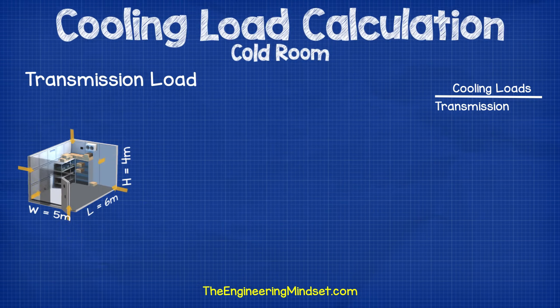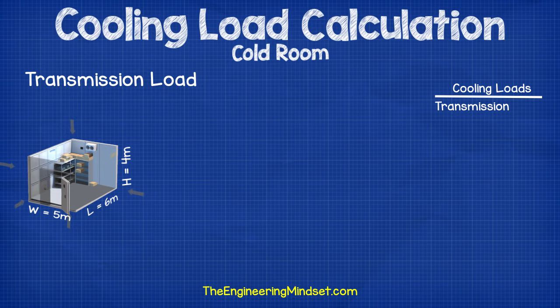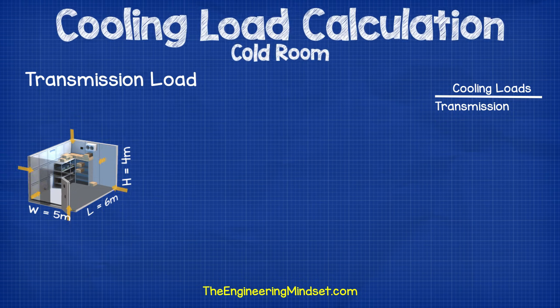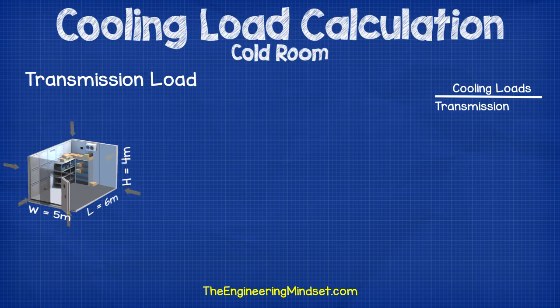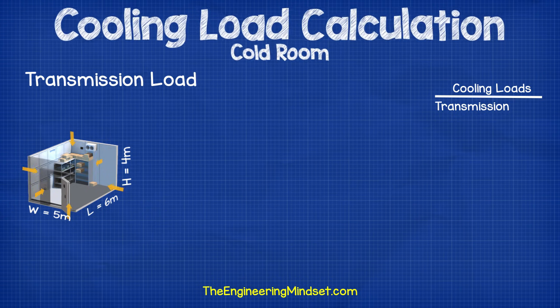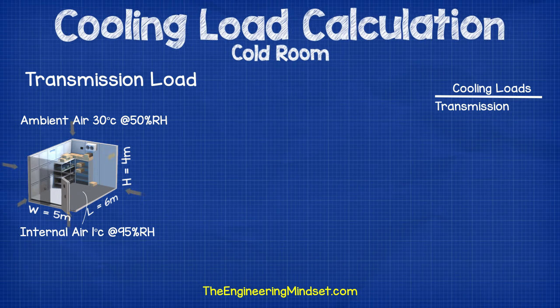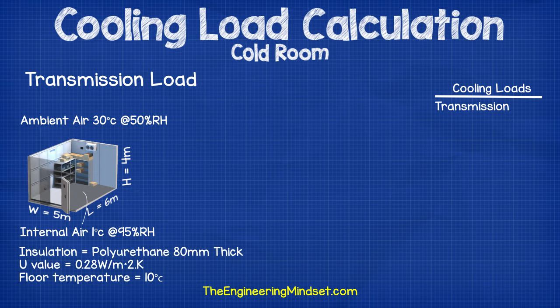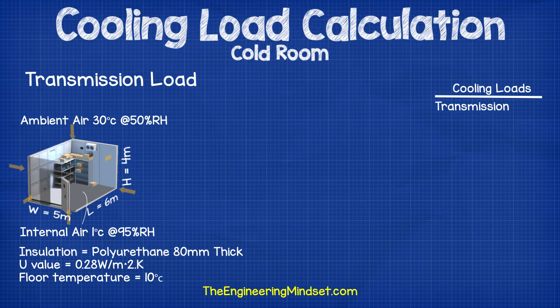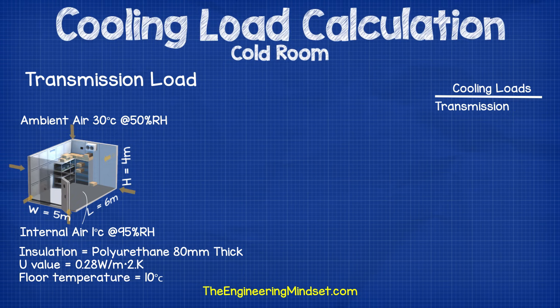So let's now run a simplified example of a cooling load calculation. If you're doing this for a real-world example then I recommend you use design software such as the Danfoss CoolSelector app for speed and accuracy. First of all let's start with the transmission load. The dimensions of our cold store are 6 meters long, 5 meters wide and 4 meters high. The ambient air is 30 degrees Celsius at 50% relative humidity and the internal air is 1 degree Celsius at 95% relative humidity. The walls, roof and floor are all insulated with 80 millimeters of polyurethane with a U-value of 0.28 watts per meter squared per kelvin, and the ground temperature is 10 degrees Celsius.